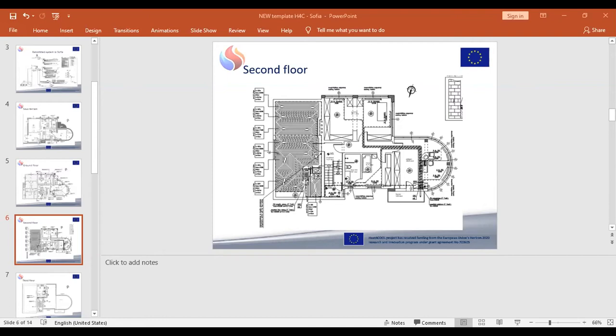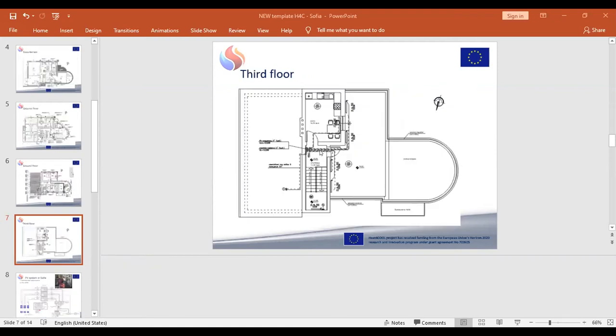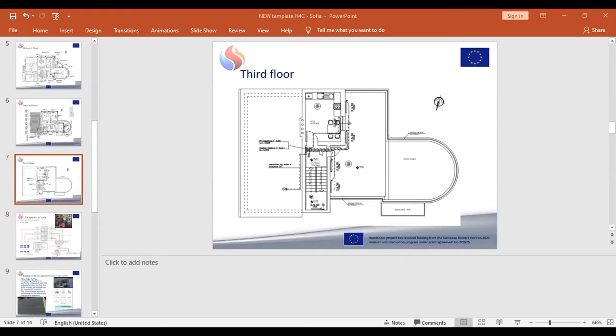For each heating zone, the following facilities are installed in the vicinity of the gas boilers. A two-way vertical on-off motorized zone valve implements the connection between the heat pump and the heating outlets for the given heating zone. Also, a hydraulic separator provides hydraulic separation between the heat pump and the heat outlets for the given heating zone. A three-way spherical on-off motorized zone valve directs domestic hot water directly from the heat pump to the occupants, or redirects it through the gas boiler to be heated to the desired temperature.